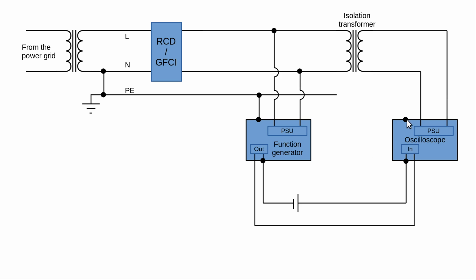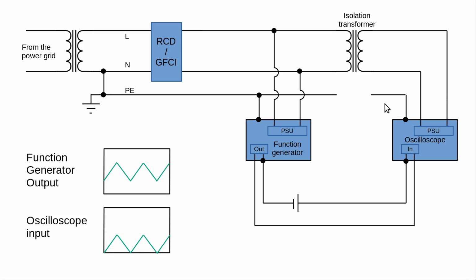And now we still have the question: what do we do with this earthing wire here? Well, we don't do anything, we just leave it hanging there, or we plug it into the box which contains the isolation transformer, and in there it won't be electrically connected. So will it work? Yes, it will work, because the earthing wires between those two devices are not connected. So we don't have a short in the battery, and the circuit will work as we've seen before. But now what will happen in case there's a fault?